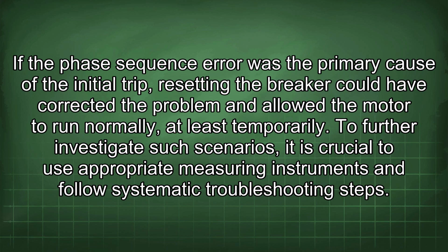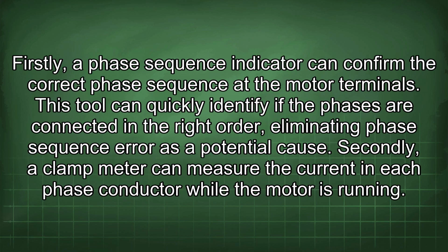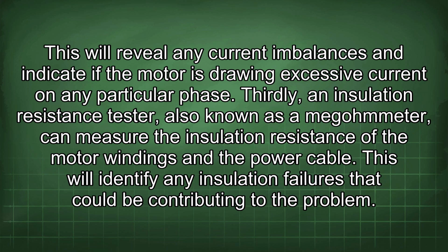To further investigate such scenarios, it is crucial to use appropriate measuring instruments and follow systematic troubleshooting steps. Firstly, a phase sequence indicator can confirm the correct phase sequence at the motor terminals. This tool can quickly identify if the phases are connected in the right order, eliminating phase sequence error as a potential cause. Secondly, a clamp meter can measure the current in each phase conductor while the motor is running. This will reveal any current imbalances and indicate if the motor is drawing excessive current on any particular phase.